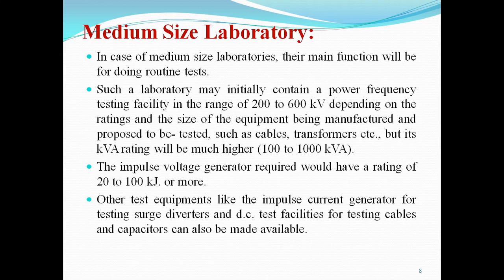Then the medium sized laboratory. In the case of medium sized laboratories, their main function will be doing routine tests. Such a laboratory may initially contain a power frequency testing facility in the range of 200 to 600 kV, depending on the ratings and the size of equipment being manufactured and proposed to be tested, such as cables, transformers, etc. But its kVA rating will be much higher compared to the small laboratory, 100 to 1000 kVA. The impulse voltage generator required would have a rating of 20 to 100 kilojoule or more.